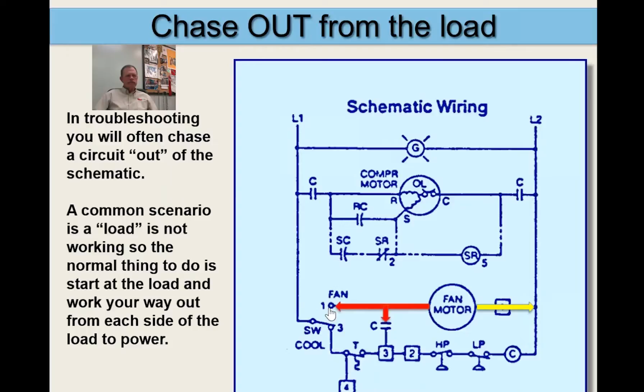But if I've got a continuous path all the way to L2, and I've got power, then the fan motor's still not working, so I chase out the other side. In this little example, it's obvious why the fan motor's not working: this switch is open, and this switch is open. There's nothing happening, so I'm not getting power. But that's what I call chasing out from a load. Or, in some cases, you can chase in from the power source.